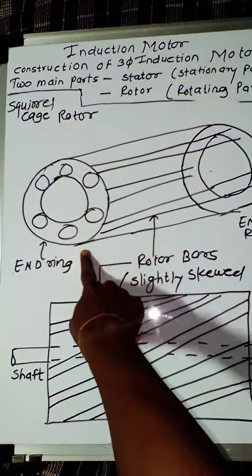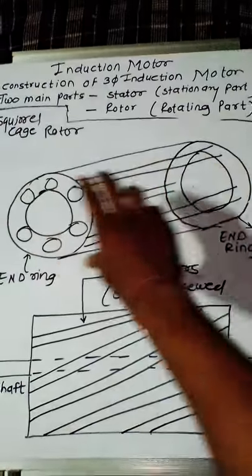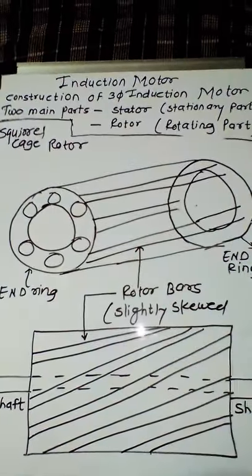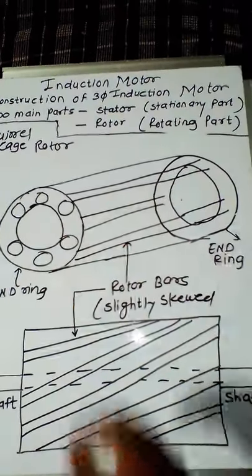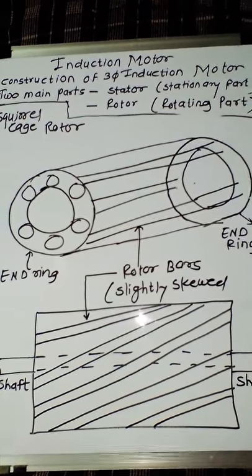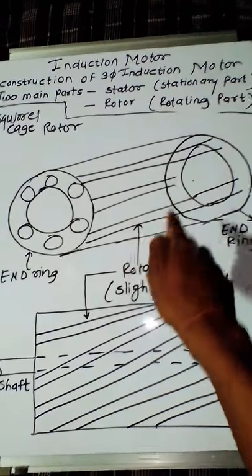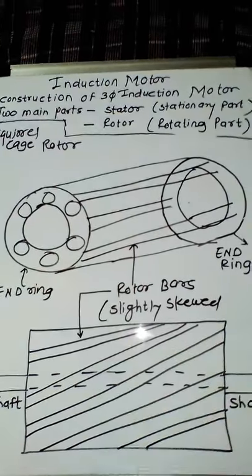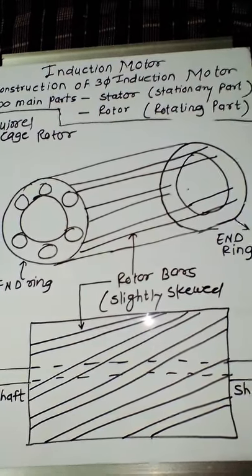The rotor bars are short-circuited on the end rings. As you can see, there are two end rings, and the rotor bars are short-circuited to these two end rings. Because the rotor bars are short-circuited to themselves, there is no arrangement to add any external resistance in series with the rotor circuit. This is a basic drawback of the squirrel cage induction motor — there is no provision to add external resistance to the rotor circuit.